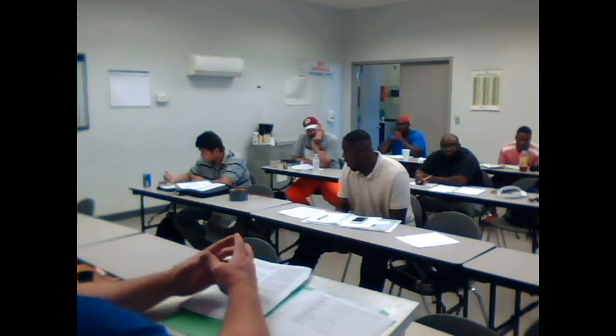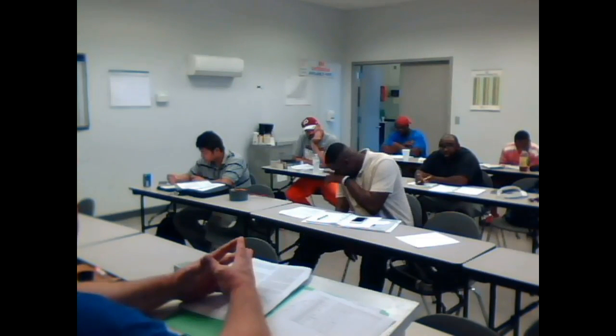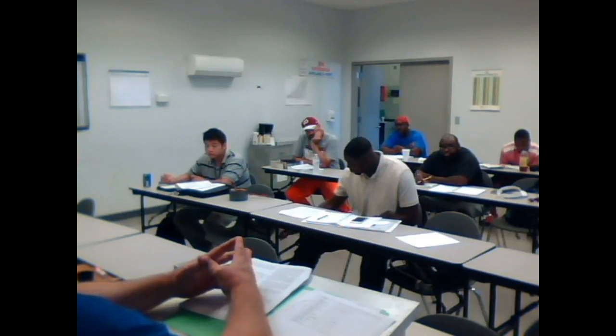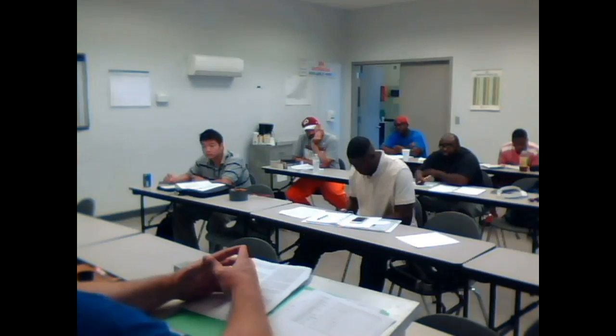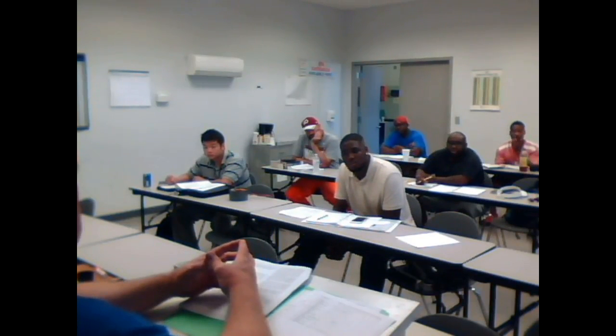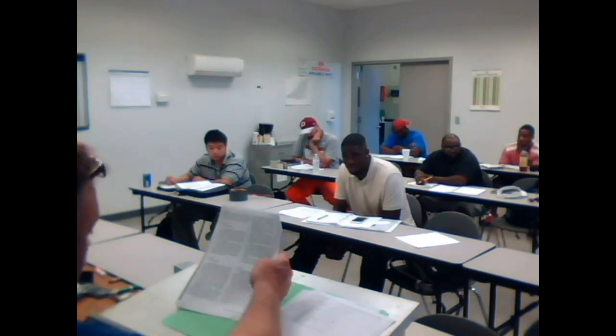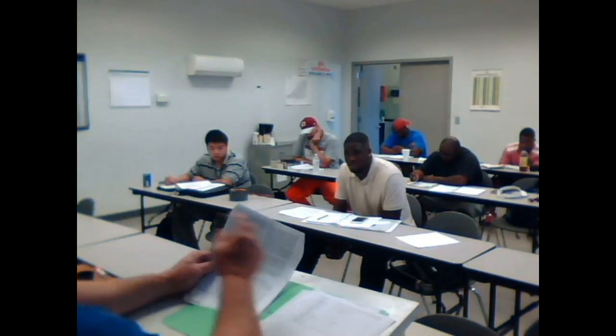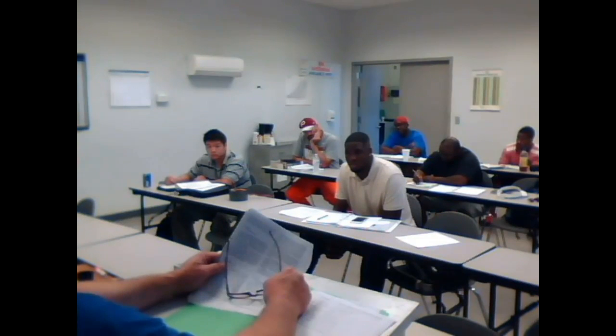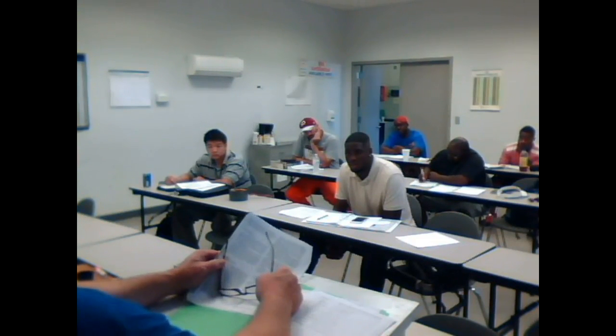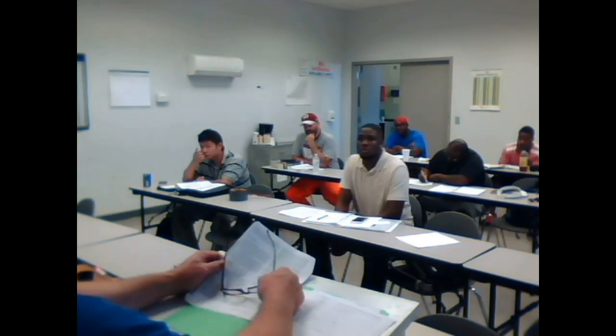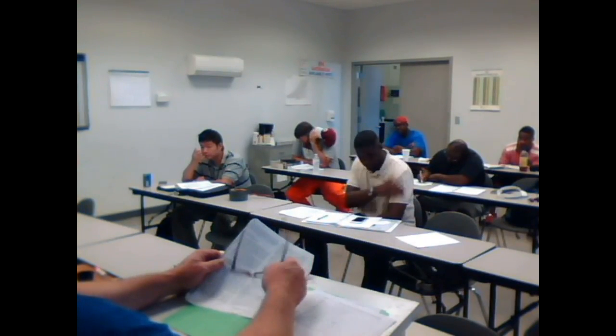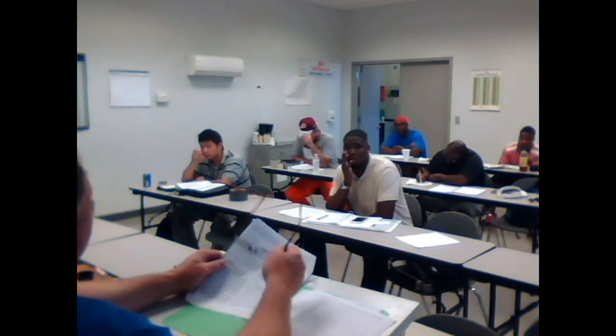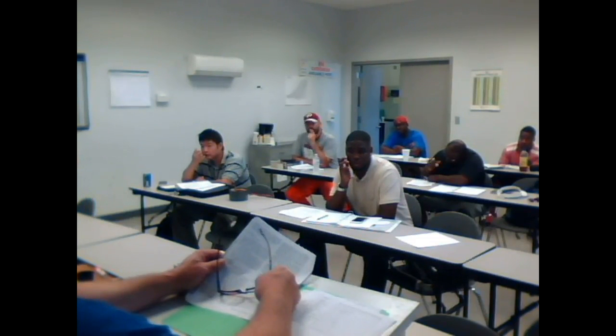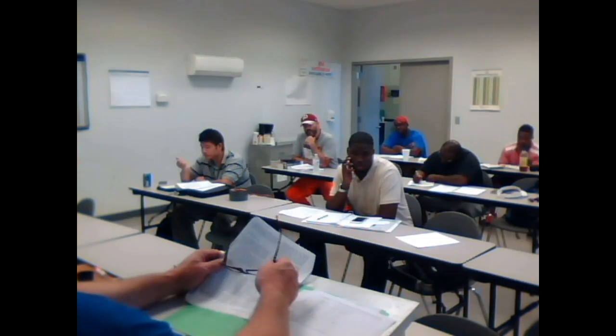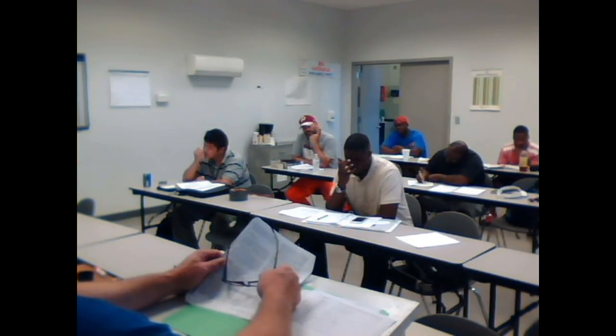But there's nothing we can do to fix it. But if you detect it, all you have to do is use your voltmeter, right? Okay. And that may not be what you came for. You came because there was a problem. You check and say, hey, my part's out, the transformer, something like that. You put it back in, you get the system running, and you wonder what caused this. And that's why you would do a voltage check, and you go, oh, this thing's way out of range.